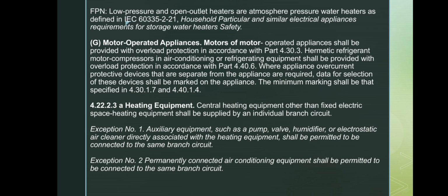At minimum, it must include the markings required in 4.30.1.7 and 4.40.1.4. For central heating equipment, except fixed electrical space heating units, it must be supplied by an individual branch circuit. However, there are two exceptions.